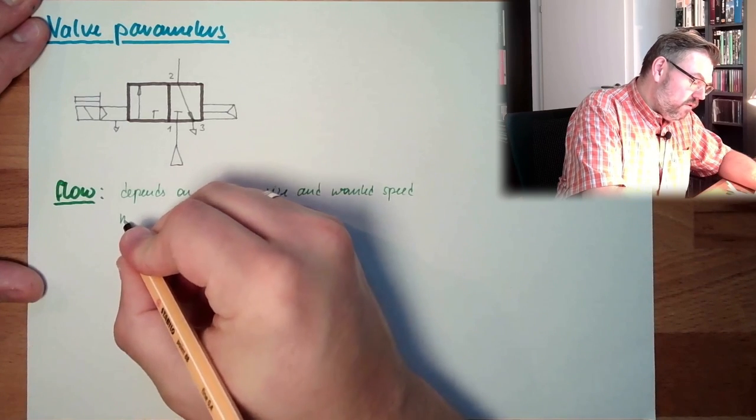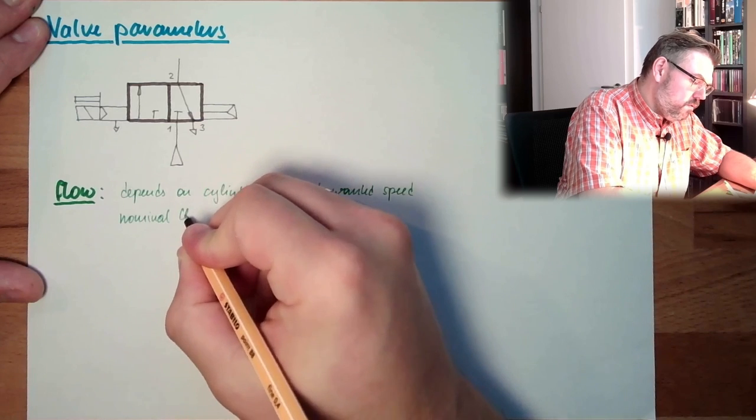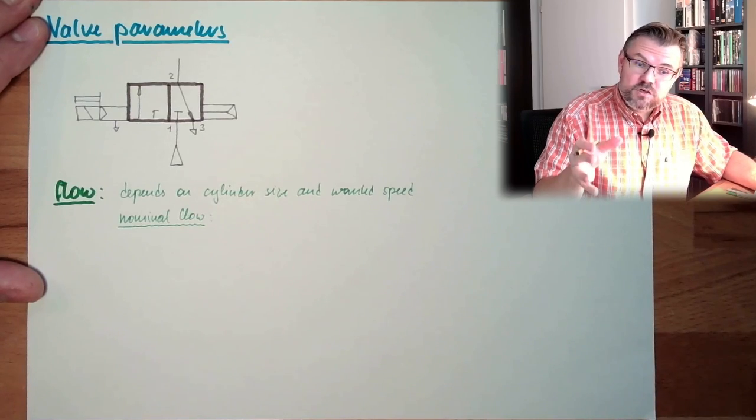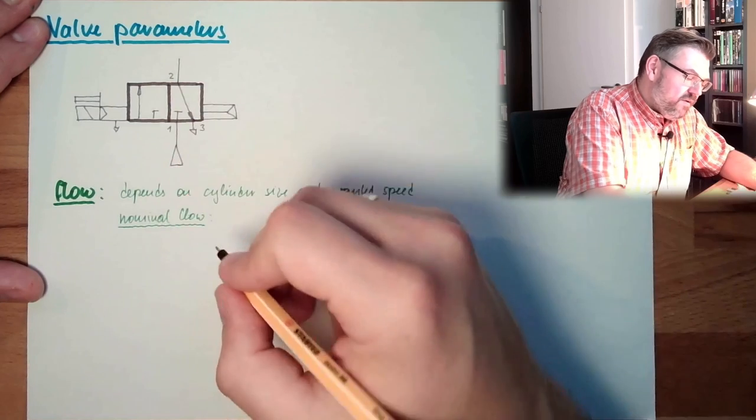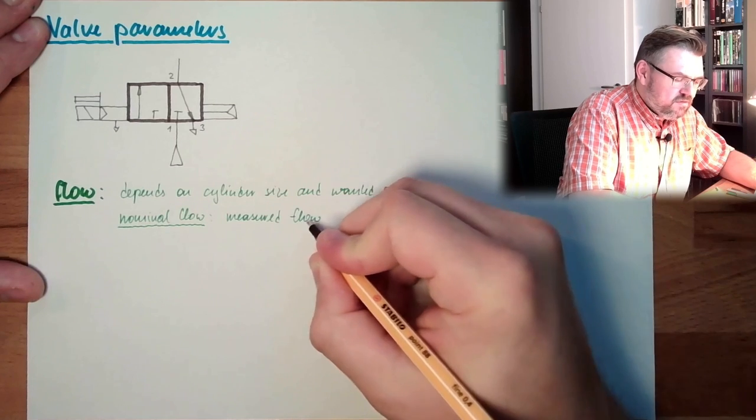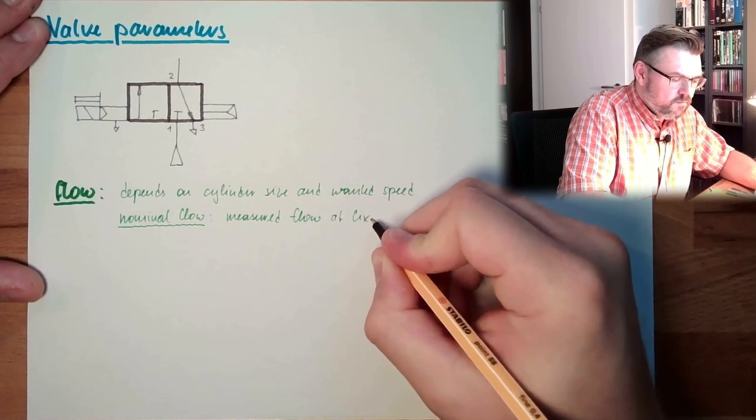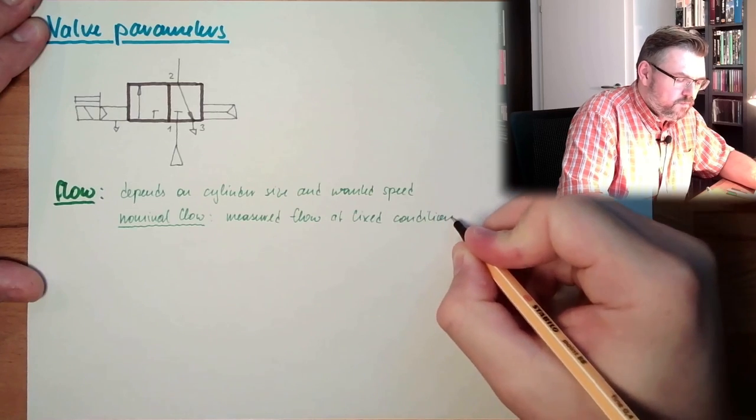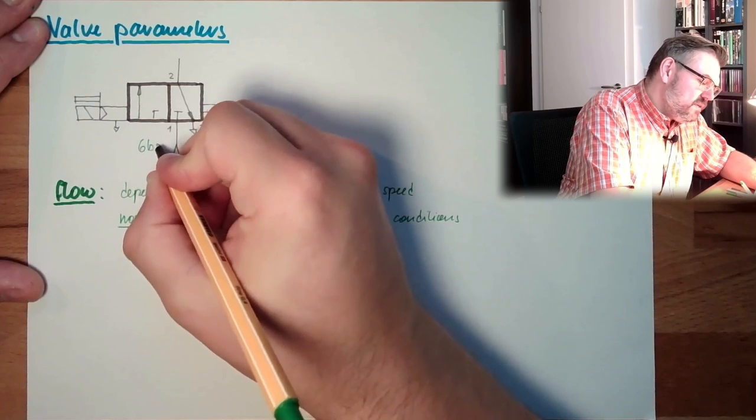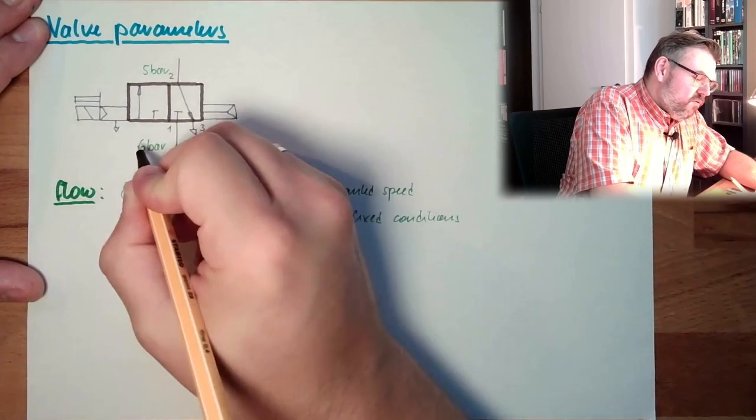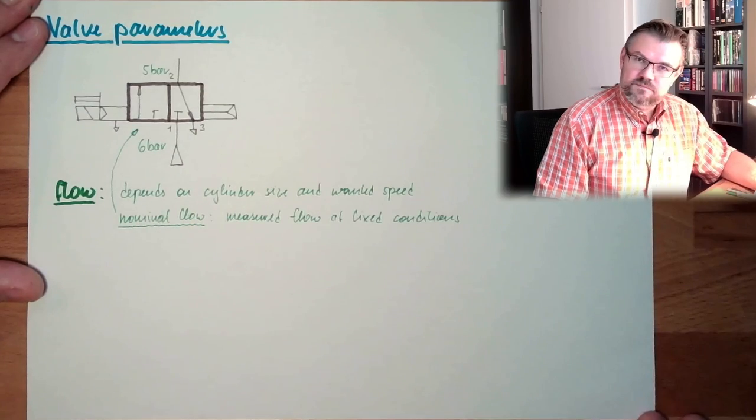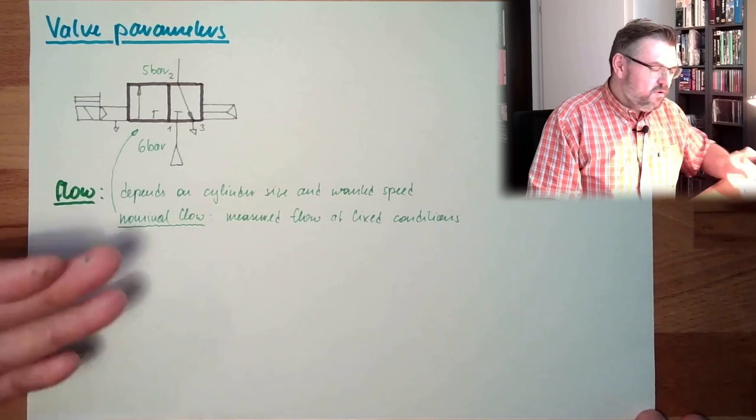Well, on one hand, there is the nominal flow. What is the nominal flow? The nominal flow is the measured flow at a fixed condition. So there are fixed conditions and we measure the flow at these fixed conditions. And these fixed conditions, in the pneumatic world, they are usually if we have in front of the valve six bar, after the valve five bar, and through the valve passing is the nominal flow. These are the conditions. If you have different levels of pressure here, then you have a different flow.